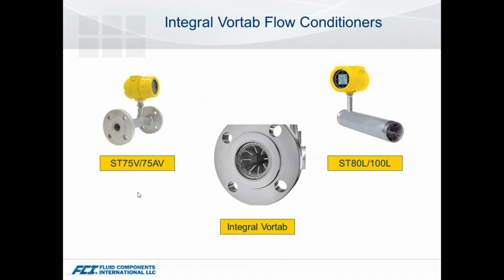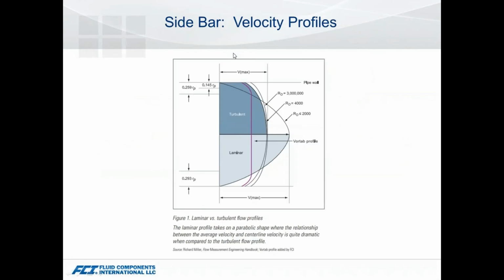The other area unique to FCI is what we call a Vortab flow conditioner. With a few of these models, the 75Vs and the 80L/100L, we have the ability to put in this integral flow conditioner as part of that spool piece design, and there are reasons for doing that. When you look at a fully developed flow profile, that's the condition we're calibrating our instruments to. Most manufacturers are calibrating for these nice fully developed flow profiles. Depending upon where we're at in the Reynolds number range, we're either in laminar flow, where we've got the nice fully developed bullet, or on the turbulent side, where it flattens out quite a bit.